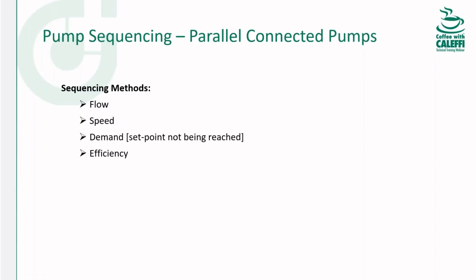One of the best things about efficiency-based staging is that it automatically accounts for changes in the plumbing system. So if the city pressure was 60 PSI when the booster was first installed, but two years later it's hovering around 80 PSI, the efficiency-based system will already account for that. Whereas the other scenarios can't handle that as well.